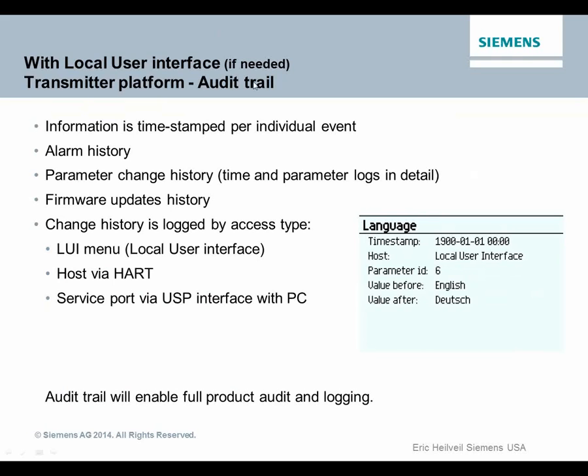Almost last but not least is an audit trail function within the device. If your device is installed and you want to make sure that people or lab techs or whoever you have out there are not messing with the device, every change and every interface with the device is logged. So in this particular case, you can say that somebody went in, this is who went in because it's the password they used, and they changed from English to German language. So if there's a problem and something changed, you can see when it was done and almost who did it.